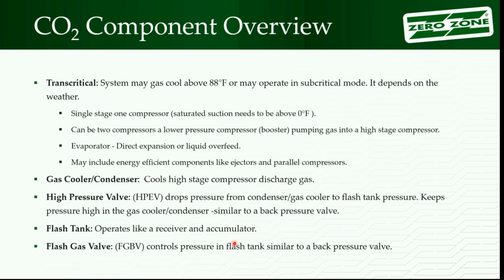So you could come upon the thought that transcritical systems always have booster compressors, because every system you've ever worked on had a booster compressor. Well, that's only because you've always worked on systems for ice cream or something else like that. If you have a warmer application, say you go out and work on an ice rink, that's above 0, right? We don't need to be below 0 to make ice in an ice rink. You may only have a single stage compressor with that.